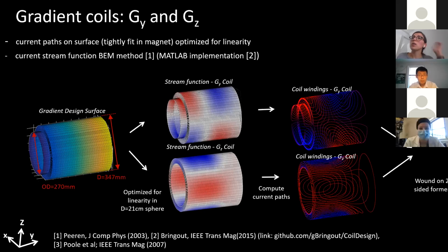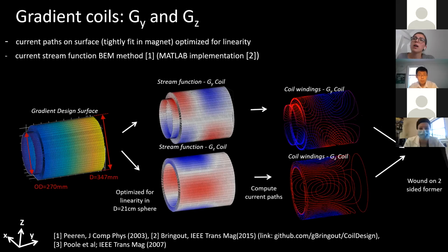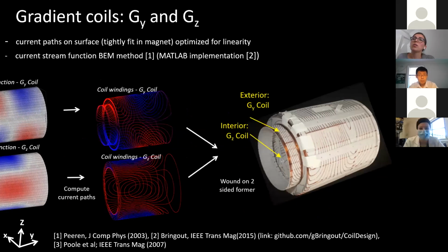And to design the coils, we optimized the current path on the inner and the outer surface of a 2-tiered cylinder, which tightly fits into the permanent magnet. And the current path was optimized to create a linear field for those encoding directions. So first, the current density is determined with a BEM stream function method. And then we convert to realistic winding patterns. And then finally, we construct the gradient coil.